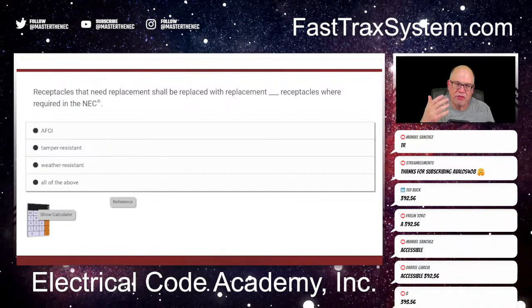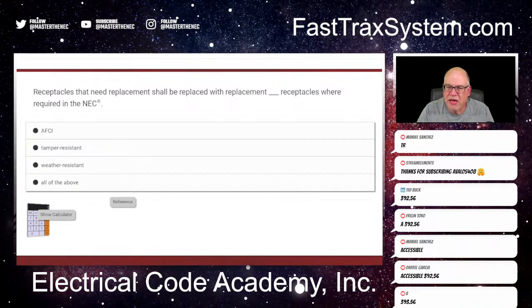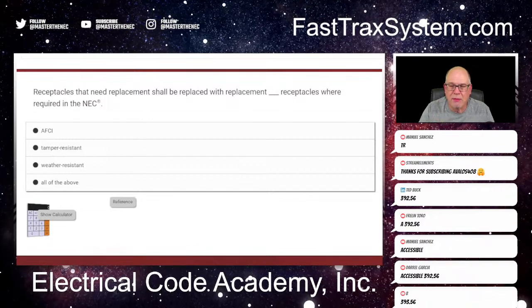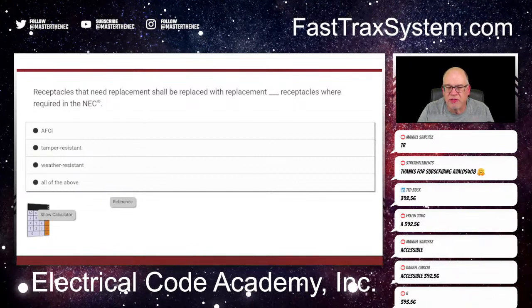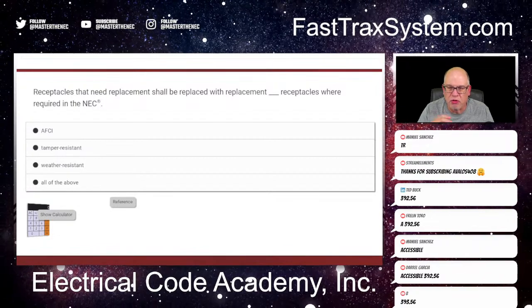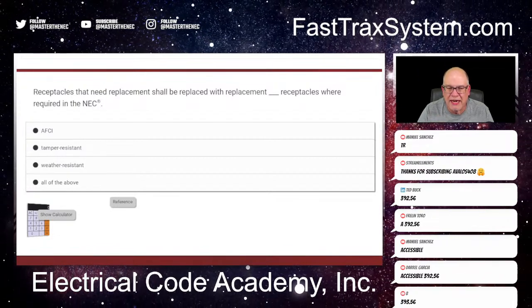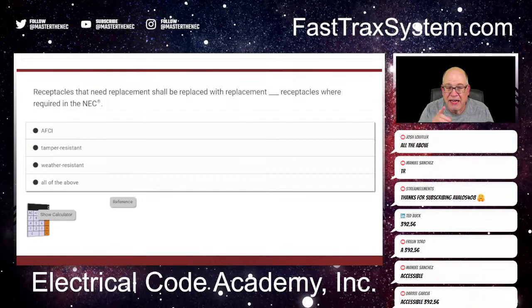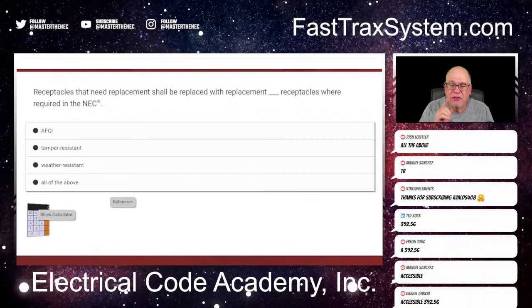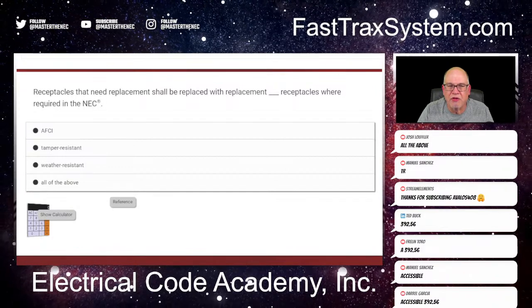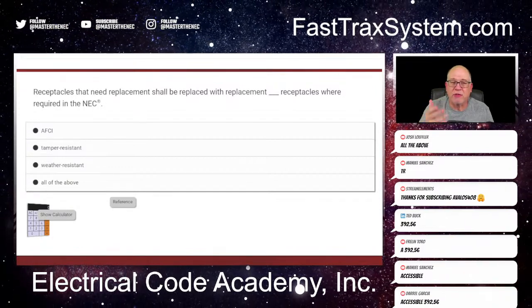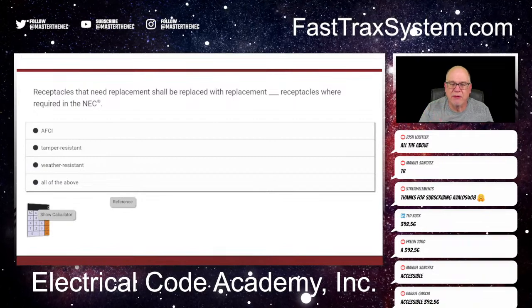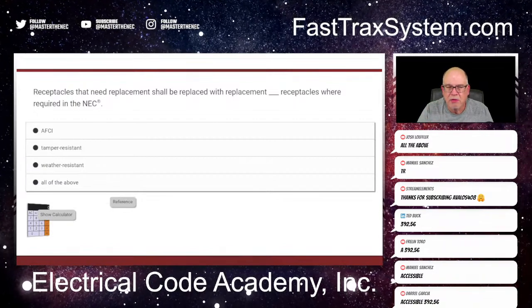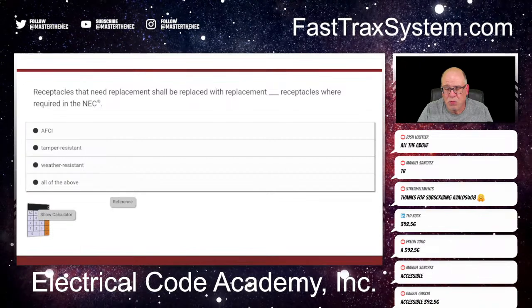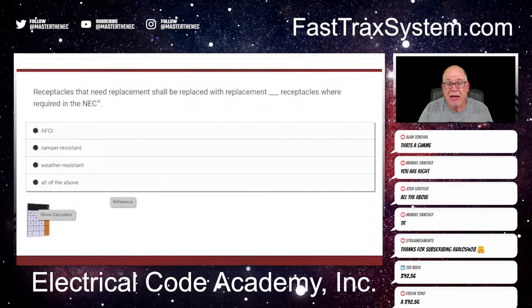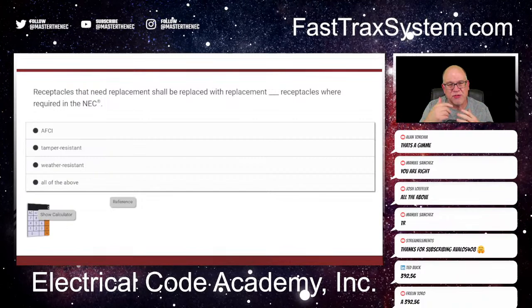So Manuel says tamper resistant, but Manuel, let me ask you this - if you install the receptacle in an outdoor location, is it not also required to be weather resistant, a WR rating? If I install a receptacle in a location that requires AFCI protection and I'm replacing the receptacle, does it not require it to be protected by AFCI? So at the end of the day, what do we got? We've got multiple choices. Alan says that's a gimme.